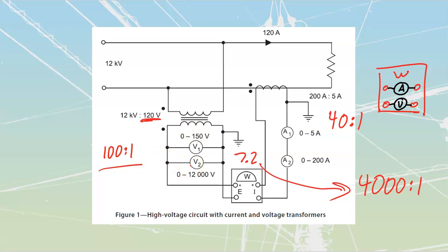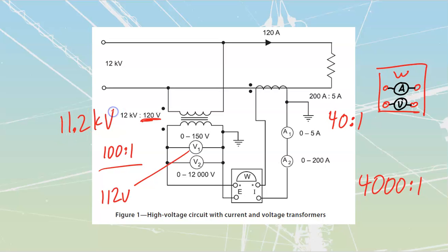My voltmeter itself is going to have a multiplier of 100 to 1. If I see on this that I'm coming in at a value of, let's say, 112 volts, that would tell me that I could take 112 multiplied by 100, which would get me out to a value of 11.2 kV over here. So, yeah, these multipliers allow us to carry these things out.